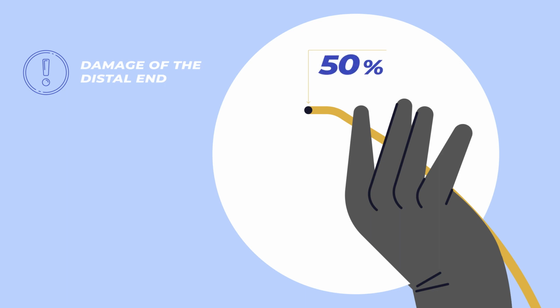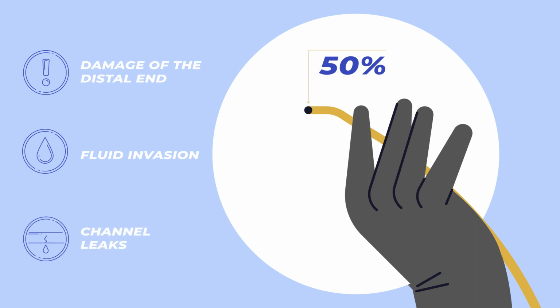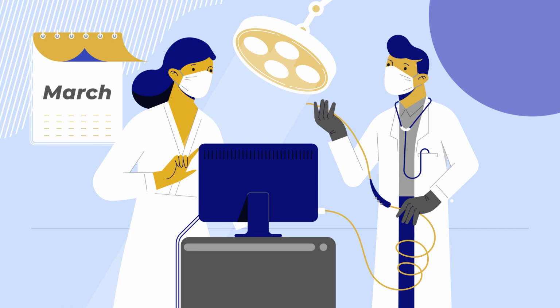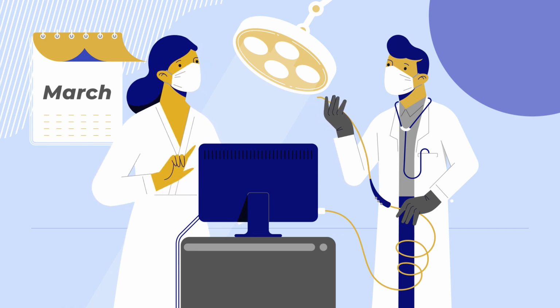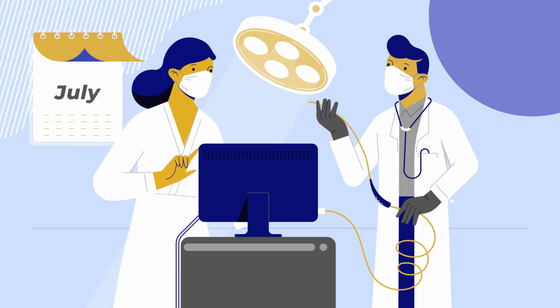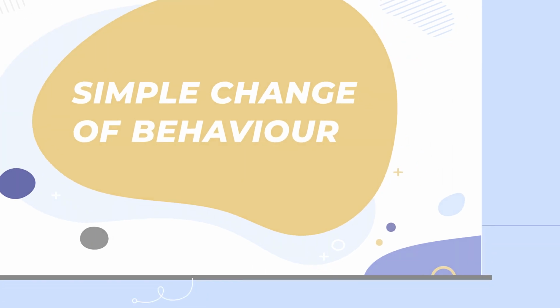Did you know that one of the most important parts of an endoscope is the distal end, and that's where almost half of the damage occurs? 85% of endoscope damage is a result of improper handling during use, transport and cleaning. So avoiding damage to this fragile part is important. It will save your team stress, minimize downtime, and keep the equipment working longer and more efficiently. Most breakages can actually be avoided by a simple change of behavior, and that's where you can help.